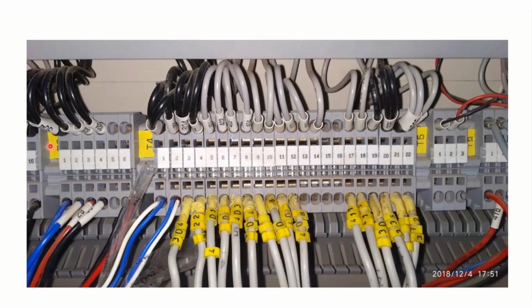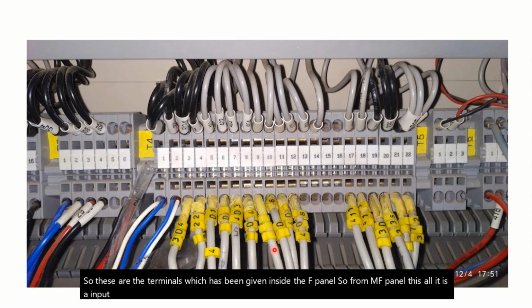So these are the terminals which have been given inside the AMF panel. All these are inputs, and the output from the AMF panel goes to the ACDB panel. There is always an integration diagram, like the DG set is generating power, and from there a power connection and a control connection both come out from the AMF panel, and it further goes into the LT panel or ACDB as per the design of the system.